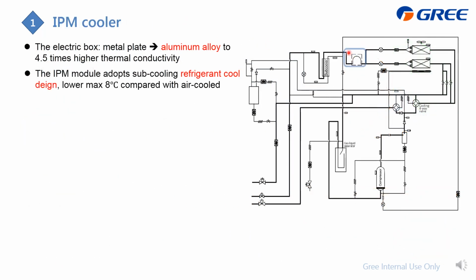The IPM cooler is located here. Because we apply the inverter compressor, lots of heat will be generated from the compressor IPM, and we apply the refrigerant to cool it down. Compared with air cooling, the temperature is max 8 degrees lower. And what we call is subcooling. It is because at this part it is completely liquid, either heating or cooling.